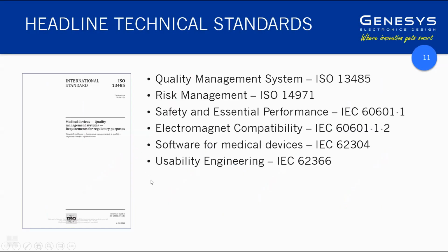As we mentioned, really the big difference between medical devices and others is the regulatory burden. And in the active space, there is a whole raft of standards that you need to be across. We're just going to briefly, as an introduction, touch on some of these particular standards. I guess the headline one is the quality management system, ISO 13485, which I've mentioned a few times already. That's what you need in place to be a medical device manufacturer.